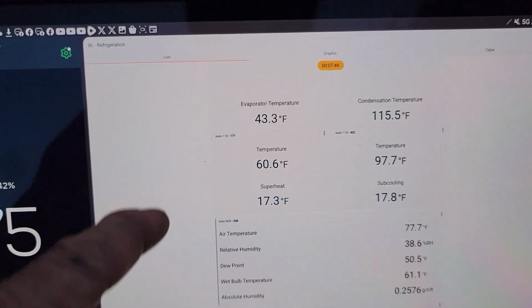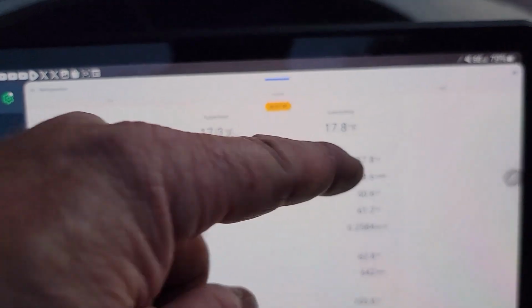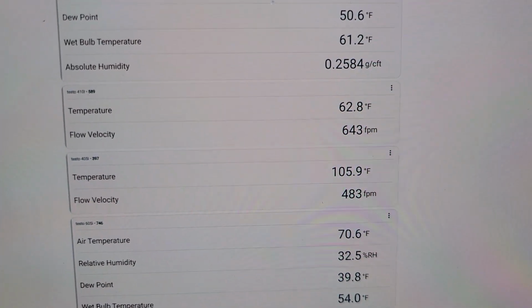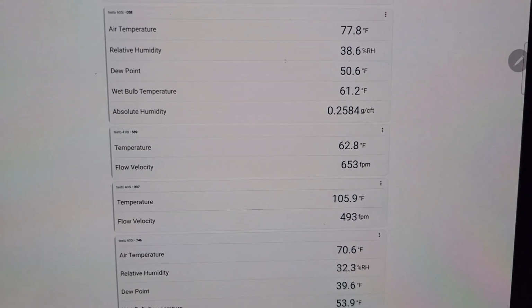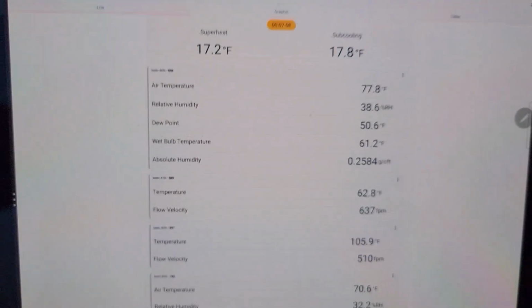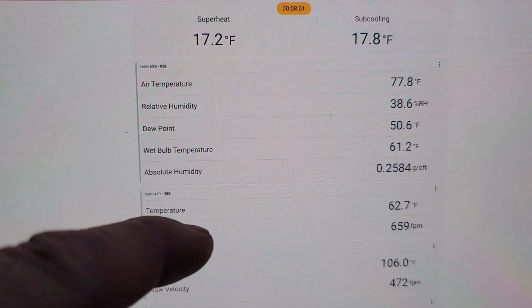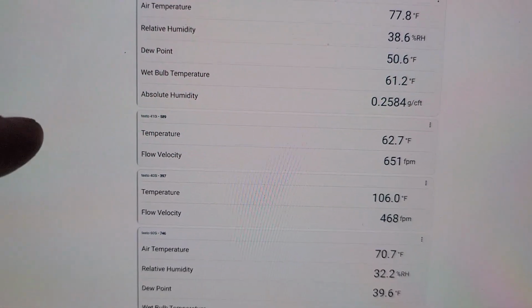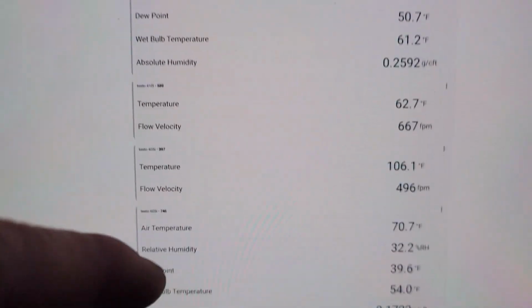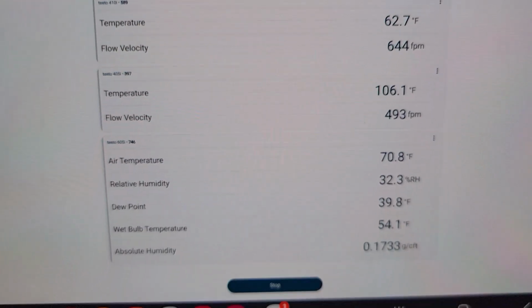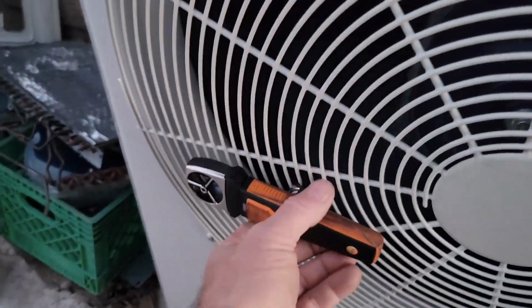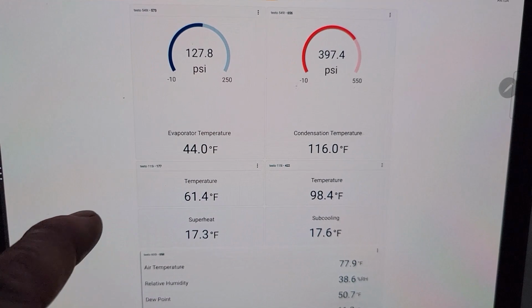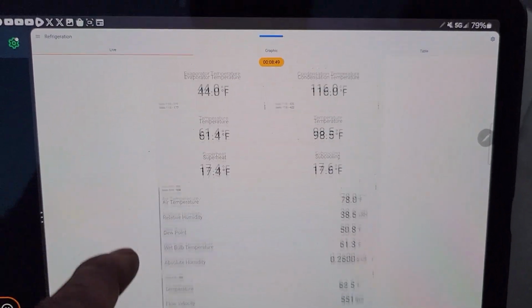So that's all good. And now my 77.8 inside is warming up with it blowing 106 degrees out the vent. So what is that coming out to? It's almost 30 degrees, because right now we're in the warmer time. And then out here, 62.7 out the front, and 70.8 for the return. So 70.8 over there, 62.7 here. Feels mighty cold. So she's making good heat. I didn't put one on the hot gas line, but I'm sure it's pretty hot.